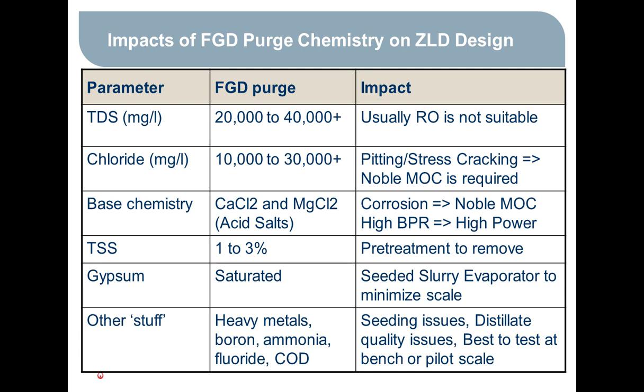But generally, RO is not a good candidate to treat FGD wastewater unless you do lots and lots of pre-treatment. So it's generally not used. Chlorides are so high that you really have to be concerned about the materials of construction and the pitting and stress cracking that occur because of high chloride concentration. So we get into some very noble materials of construction.